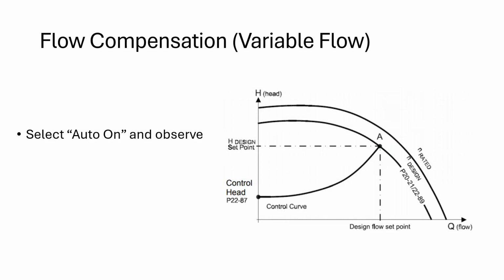So flow compensation mode, variable flow. So you select auto on and observe. So boom, you got the pump running at full flow rate, and it's supposed to be hitting a certain point to hit your design flow set point. So you see how the system's running. And actually, once you get familiar with these pumps, there may be a possibility that the startup and balancing of the system might be a little easier. So we'll see if we can talk you into that, right?